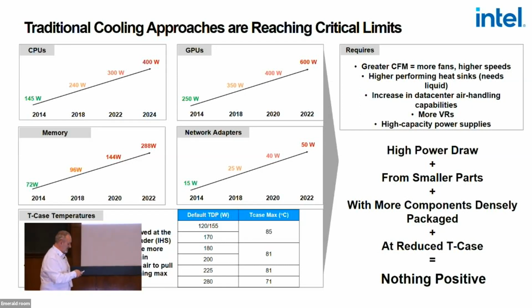Another issue causing problems is reducing T-case temperatures. Due to the increasing density of processors and GPUs, the T-case temperature is getting lower — where it used to be about 82 degrees Celsius, it's going down to 65 in the next generation. That's going to cause an even bigger issue for air cooling than we already see.